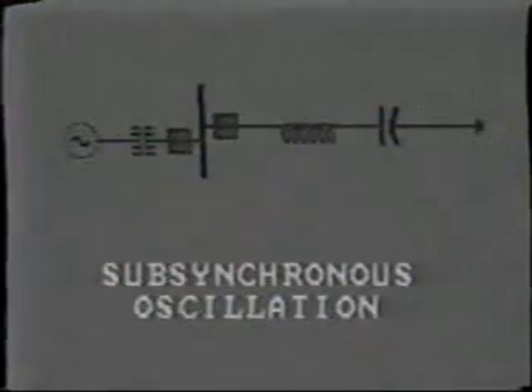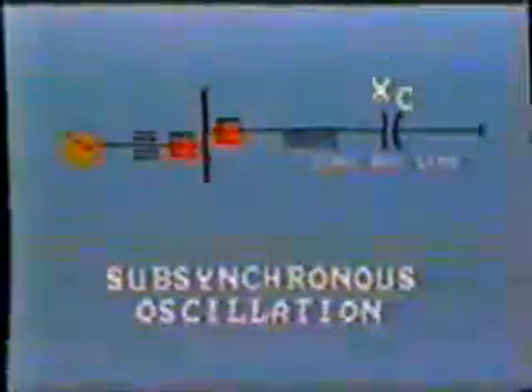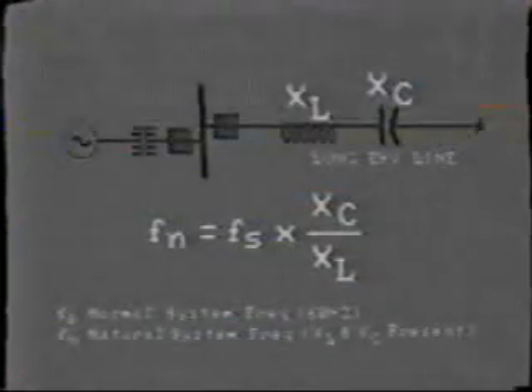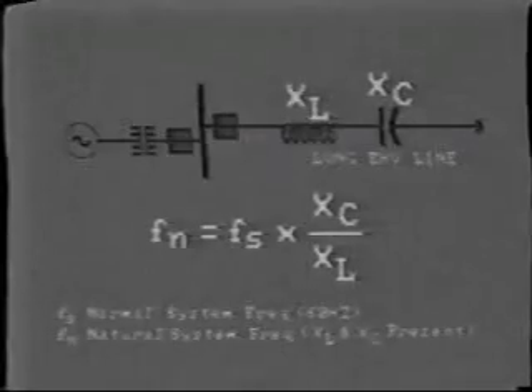You may come across the term subsynchronous oscillation in your work. What's this? Well, this complex problem may occur in rare instances where the generator is connected to a long EHV line, which has series capacitors in the line to compensate for line inductance. The effect of these capacitors is to raise the natural resonant frequency of the line close to the synchronous frequency of the generator. As a result, some oscillation is set up in the generator. This gives rise to overheating in the generator and may even lead to mechanical damage due to oscillating torque on the shaft. A special relay is sometimes installed to detect this condition.